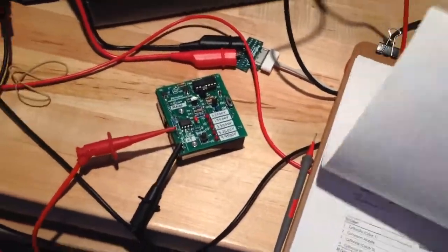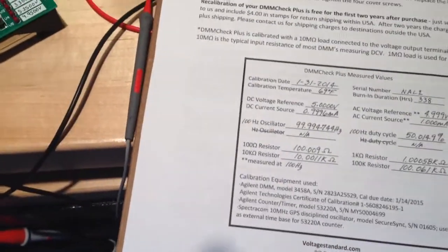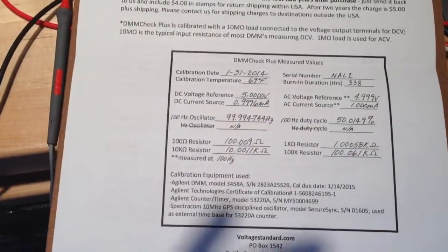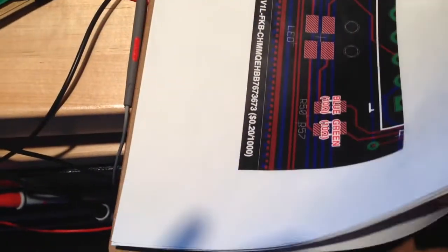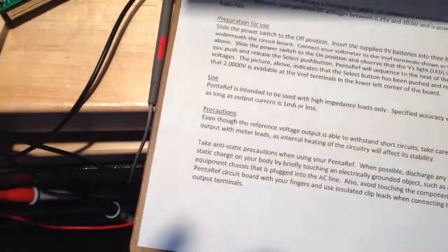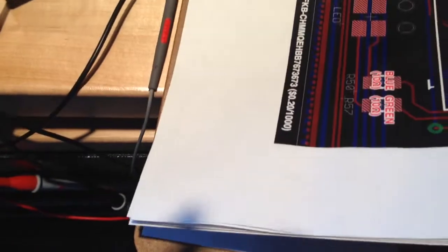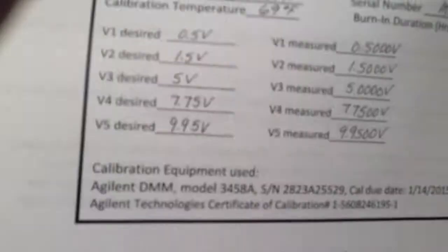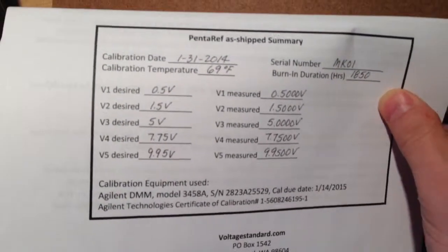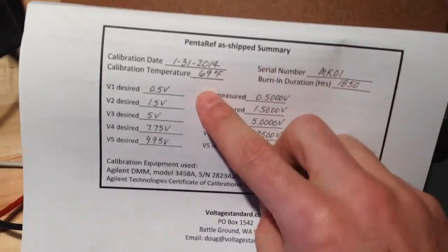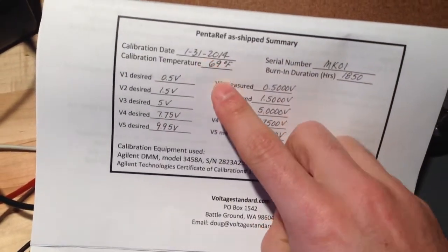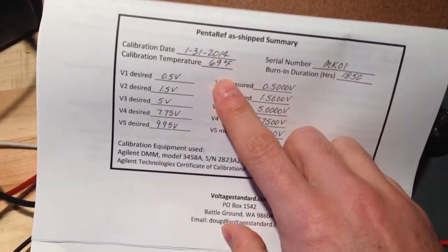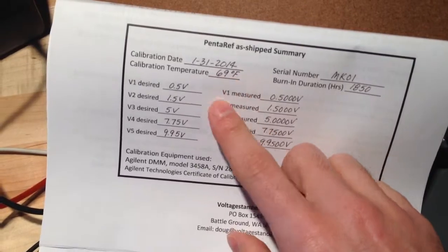It also ships with a calibration certificate that tells you the different values it was calibrated to. The neat thing here is that on the back side you can see it was calibrated on January 31st with a calibration temperature of 69 degrees Fahrenheit.